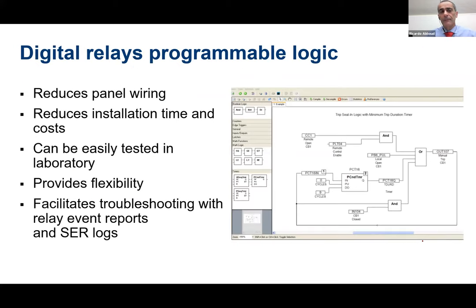So, talking about the programmable logic that we have in the digital relays. All of that logic that is done with wiring in the electromechanical relays, using association in series and parallel, using auxiliary relays, using auxiliary timers, with digital relays we can do with programmable logic. So we have AND gates, OR gates, we have timers. And also we have math variables available. I can sum, I can subtract, I can multiply different quantities that are available inside of the relay to develop new logic.